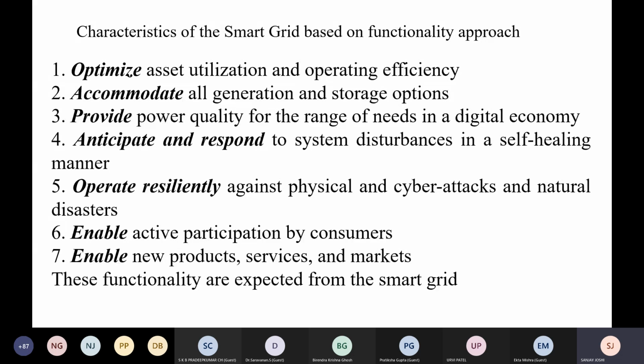The fourth one is to anticipate and respond to system disturbances in a self-healing manner. This relates to condition monitoring, which many of you are familiar with. With the help of smart grid, we can anticipate system disturbances. For example, if there is a transformer in a distribution network and its oil temperature is increasing, over a period of time, if that parameter is observed and monitored, we can anticipate that there is some problem in that transformer, and take action before an actual fault occurs within the transformer.